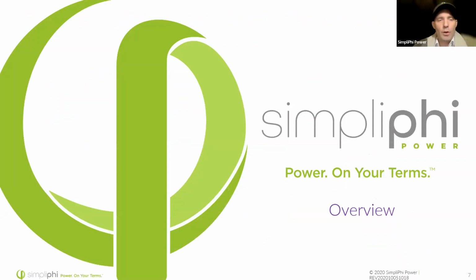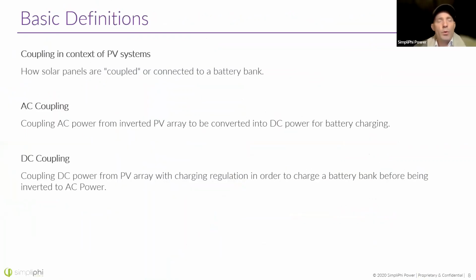So as an overview of what we're going to be talking about today, we're really planning to spend some time talking about how PV systems couple with battery banks. So solar panels are coupled to a battery bank through inverters, charge controllers, and we're going to talk about the two principal means of doing that. One of them is AC coupling, and AC coupling is really referring to having microinverters on a PV array. So PV arrays all produce DC power, but you can put microinverters on solar panels and change that DC power being produced at the photovoltaic cell level into AC 240 volts that can be directly used by the house.